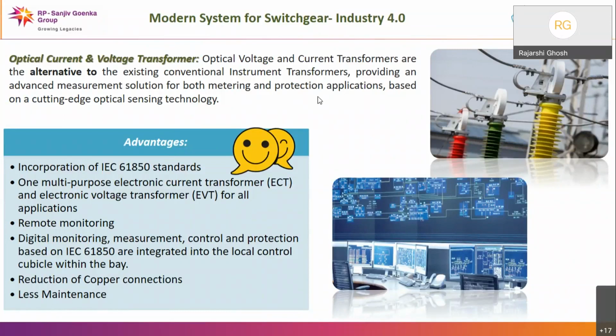In this modern system, the communication, as Mr. Ghosh has already told, between all the instruments has started playing a very, very vital role to ensure this reliability. And internationally, this IEC 61850 standard came, which we all must follow for standardization of the system.